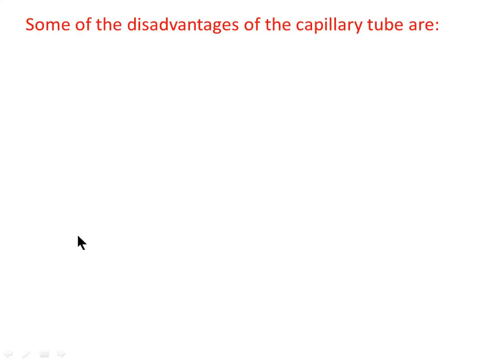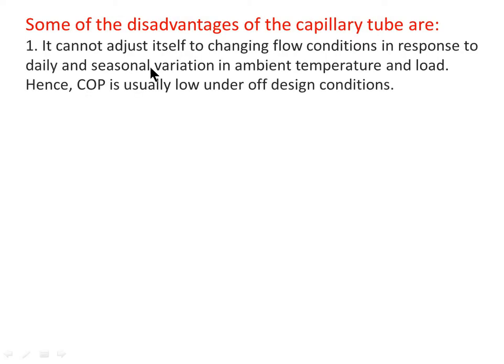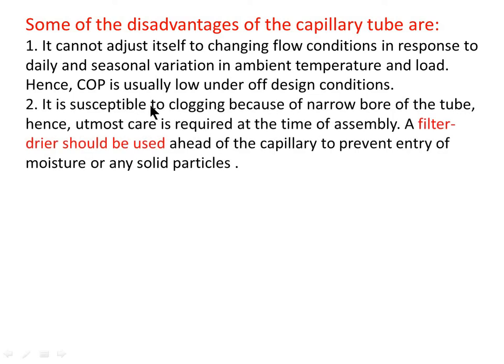Disadvantages of capillary tubes: it cannot adjust itself to changing flow conditions in response to daily and seasonal variation in ambient temperature and load, hence COP is usually low under off-design conditions. It is susceptible to clogging because of the narrow bore of the tube, so utmost care is required during assembly. A filter dryer should be used ahead of the capillary to prevent entry of moisture or any solid particles.